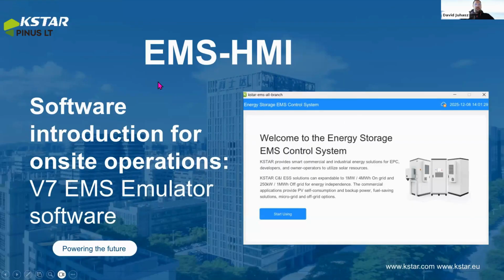And next is the EMS that I want to show you. We have the emulator software here. So when we power on the device, we see this screen. We need to configure the system first. So I'll just briefly go through that. We need to choose if we have STS or not. Let's say not. We need to select which position it is. If there is an inverter in the equipment, it's a master. If there is no inverter on the equipment because it's the second of a parallel solution, it's a slave. We choose the master now.